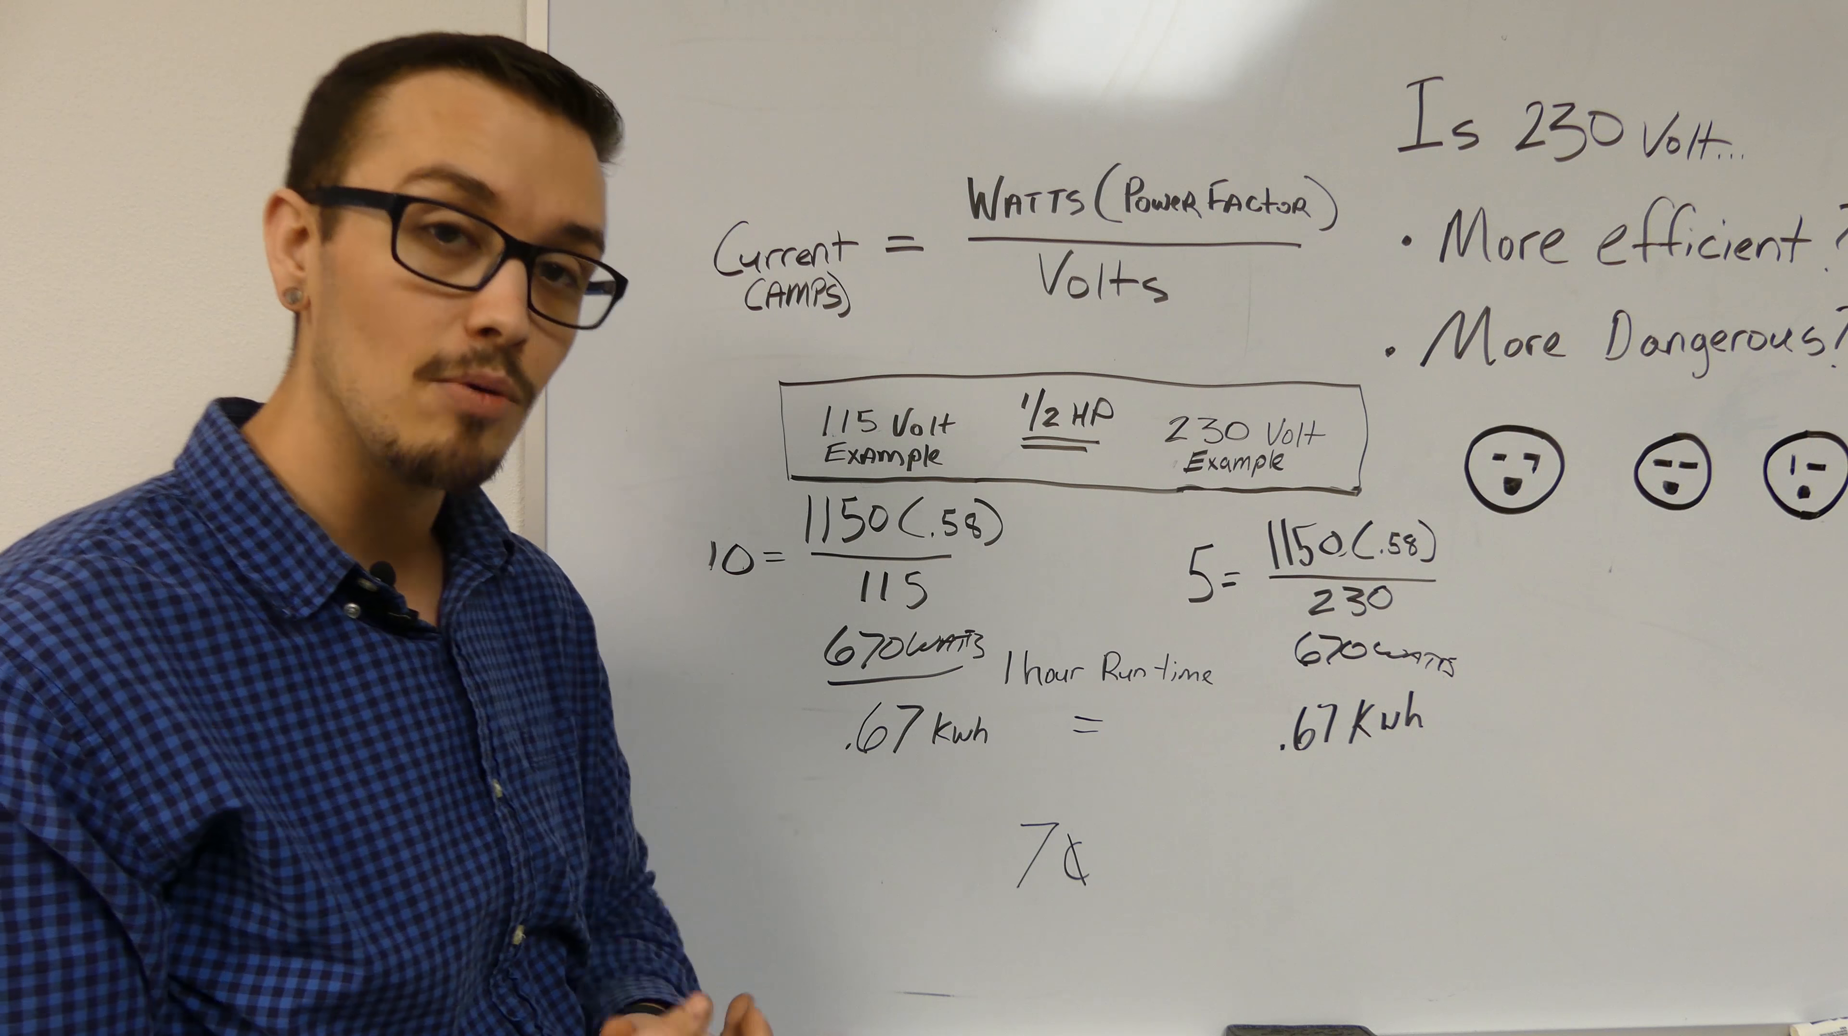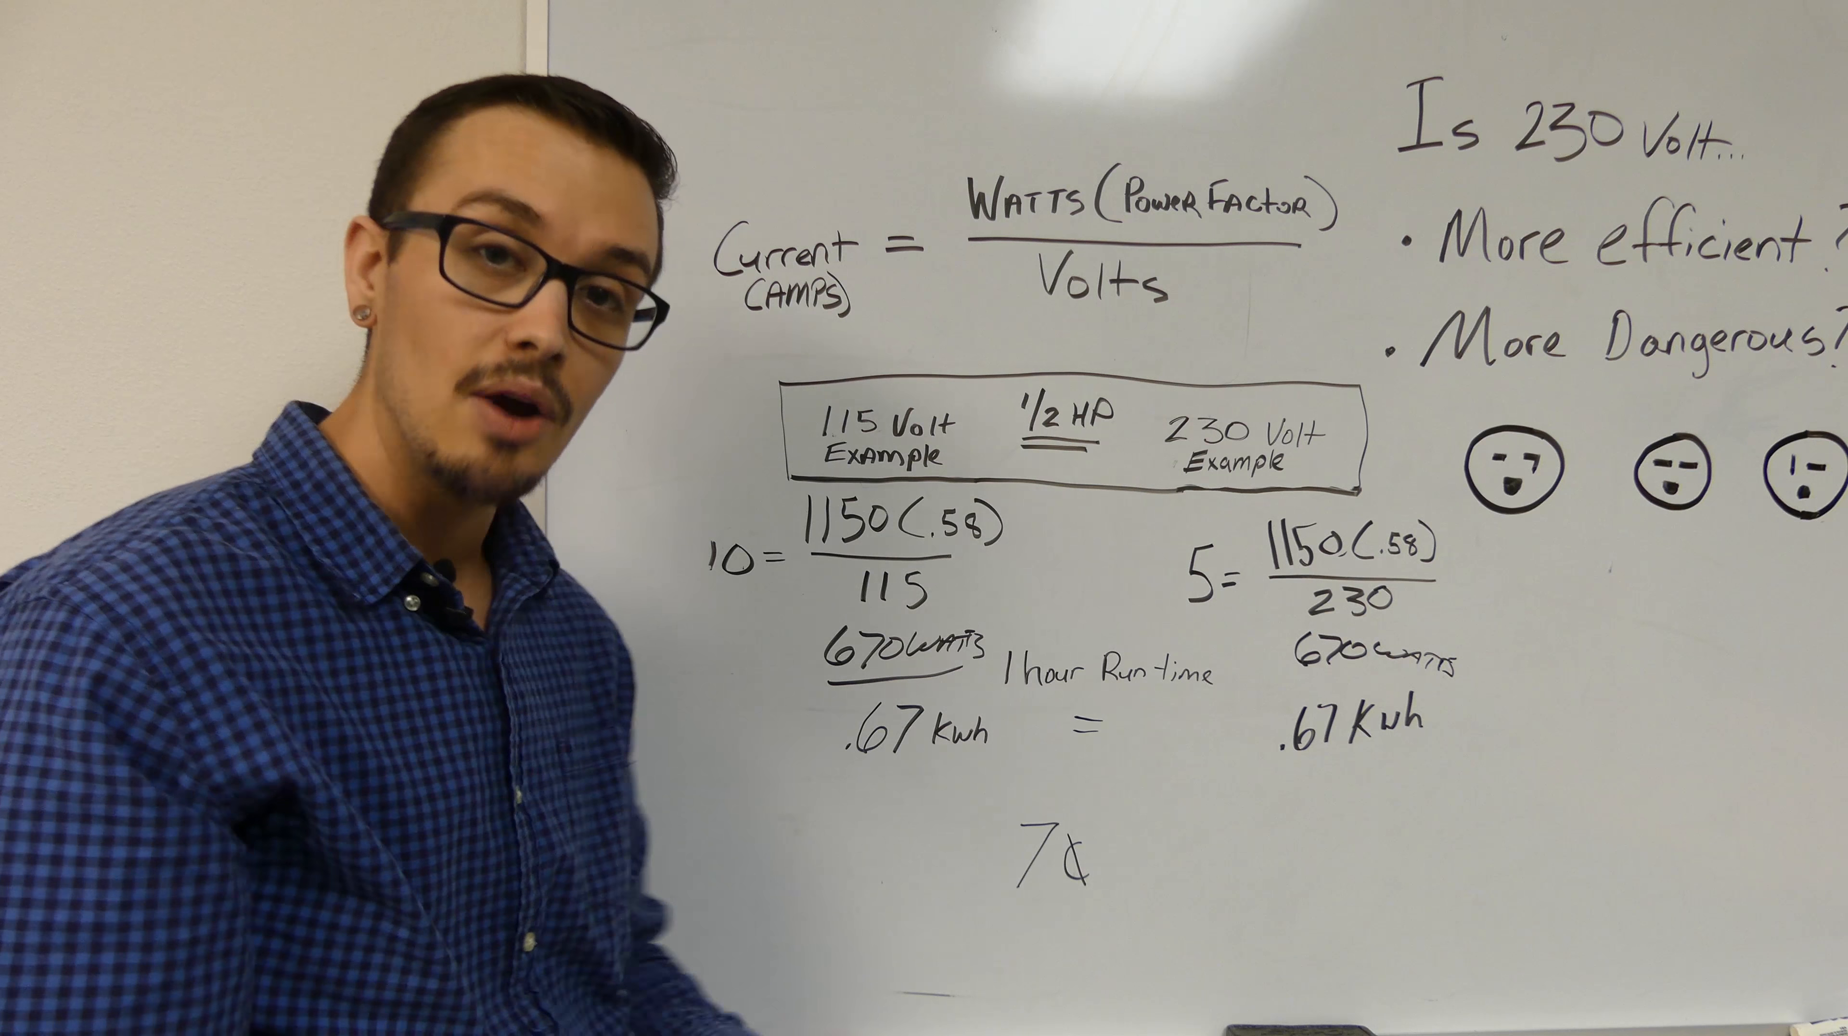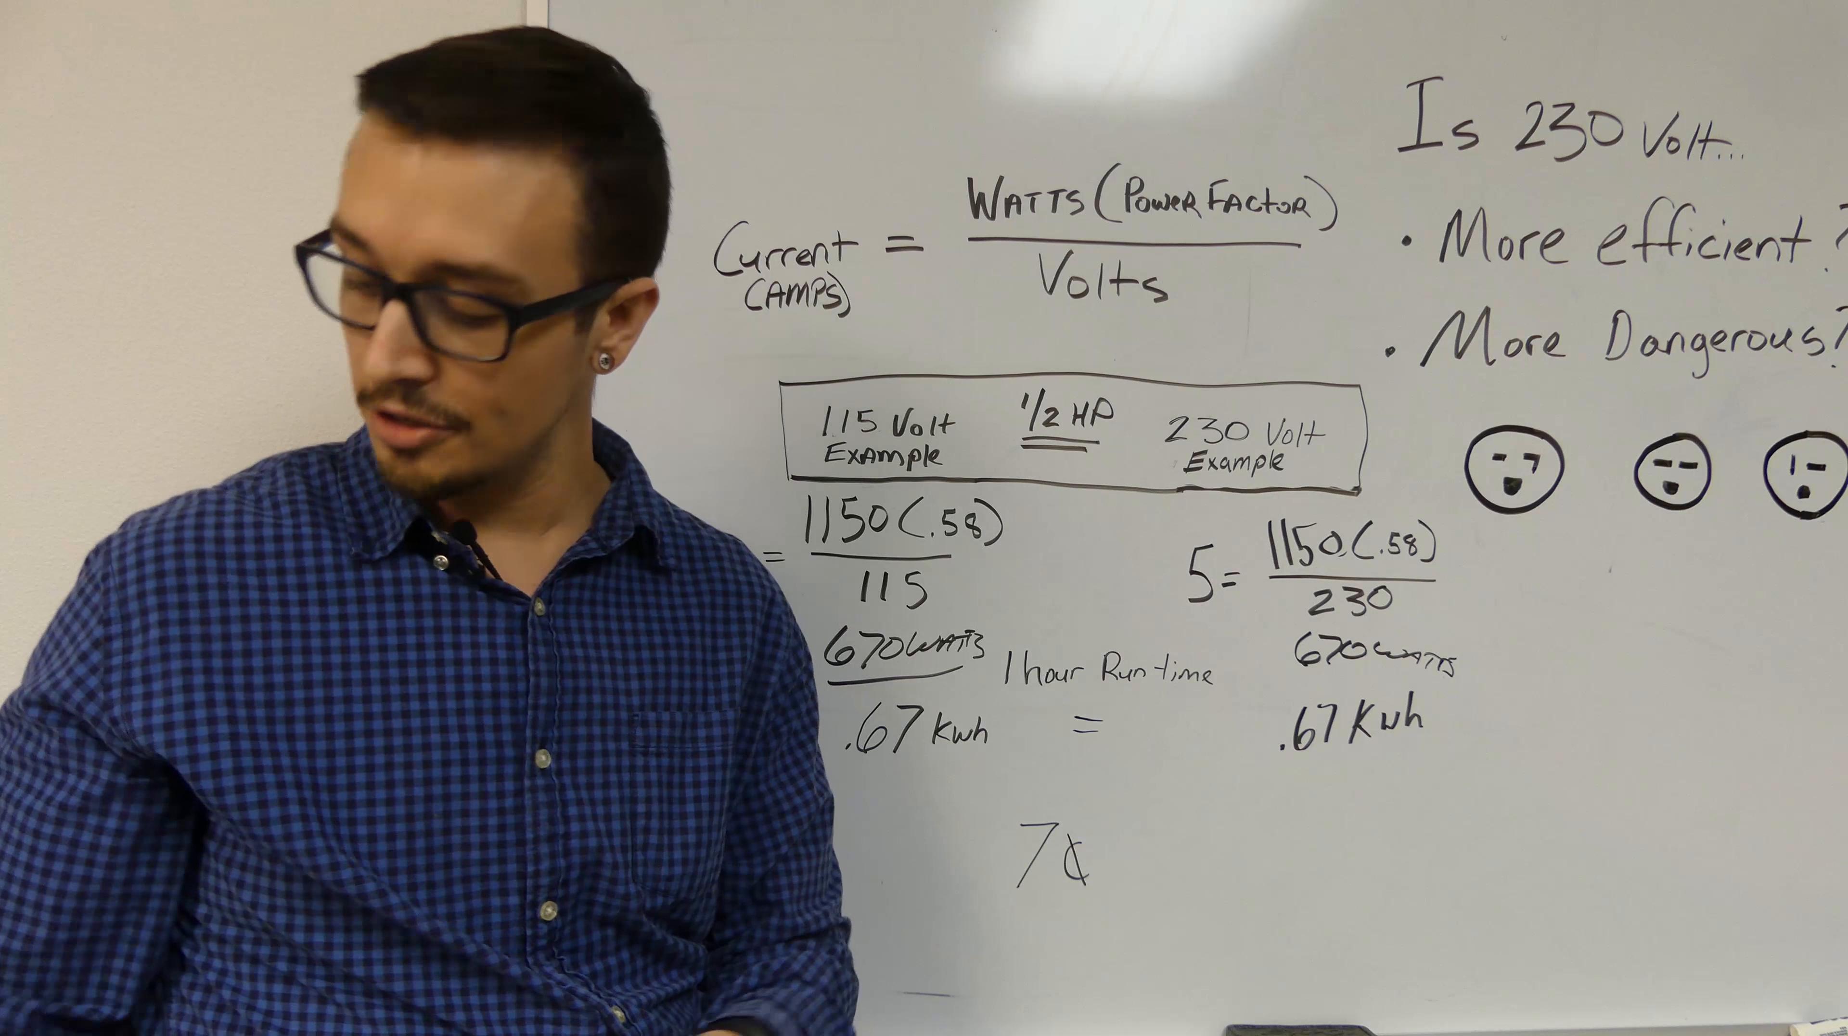Watts is a snapshot at a particular given time. If we were to run each of these motors side by side for one hour, we would multiply that out to get kilowatt hours. 670 watts times one hour equals 670 watt hours, divided by a thousand gives you 0.67 kilowatt hours. Up here in North Idaho, power's relatively cheap, about 10-11 cents a kilowatt hour. Running each of these motors would cost you about seven cents per hour. So there's clearly no advantage using 230 volt over 120 volt.